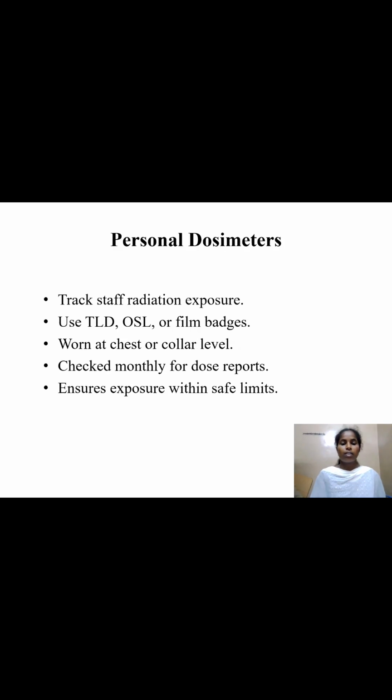The next one is personal dosimeter. Dosimeters like TLD, OSL or film badges track staff radiation exposure. They are worn at the chest or collar and checked monthly. This ensures exposure remains within safe limits.